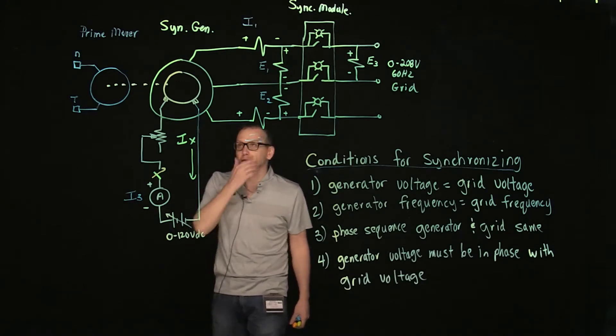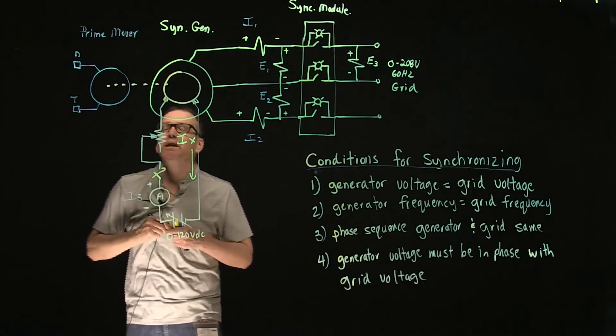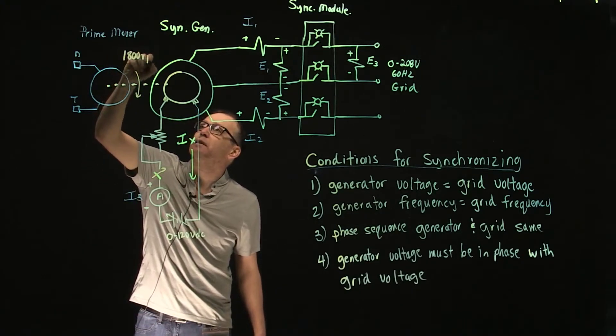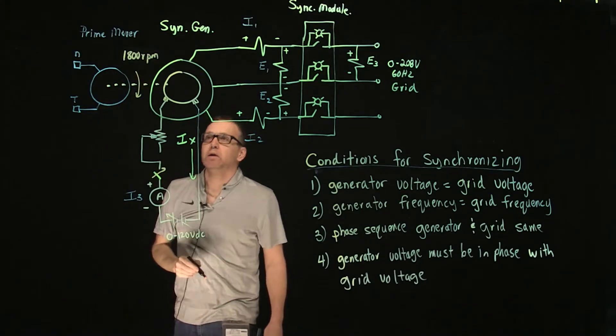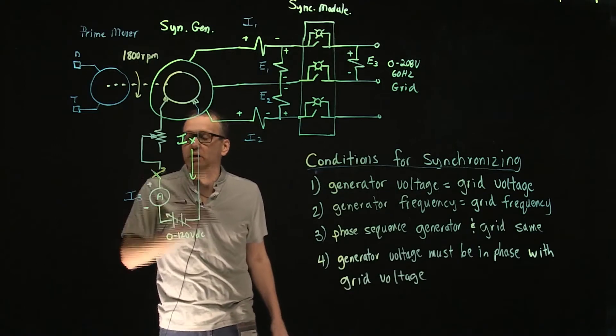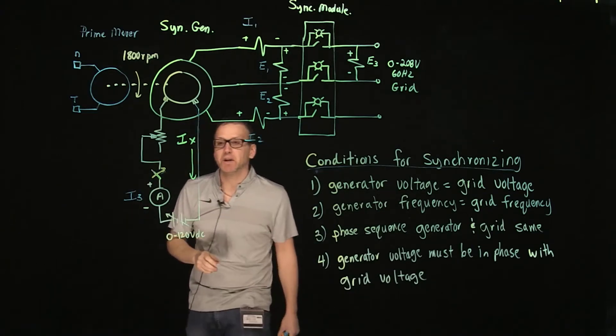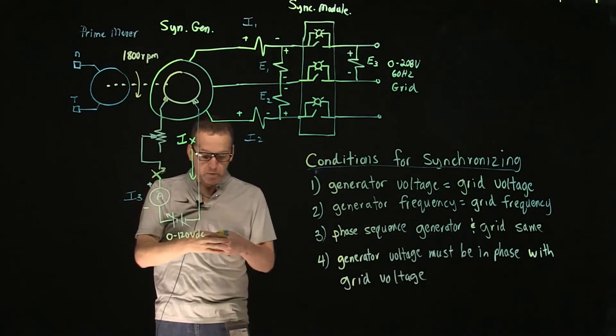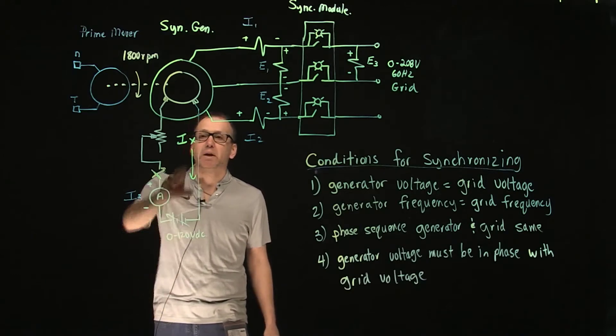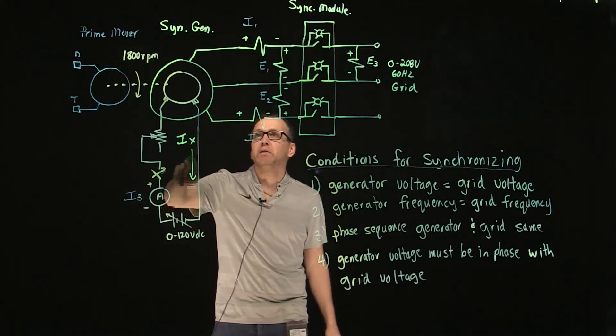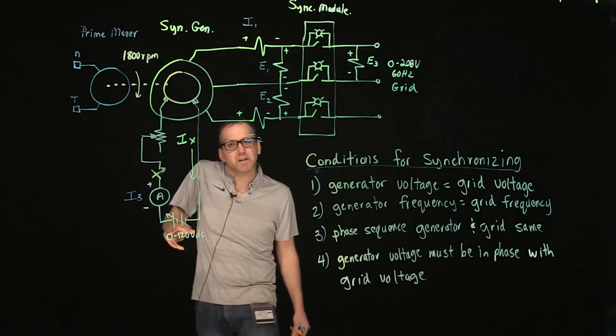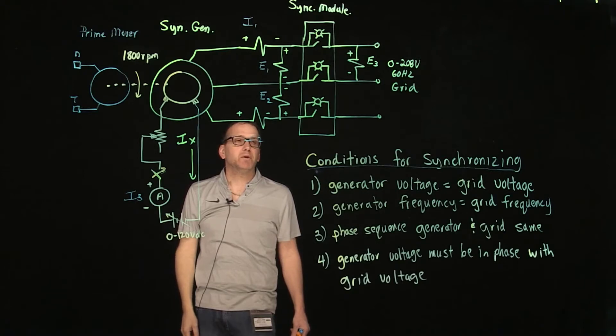The first thing we want to do is bring our prime mover up to rated speed, which in our case is 1800 RPM. Once the generator is running at rated speed, we can close the excitation switch. We can then adjust the output voltage by controlling the rheostat or the variable DC voltage to control the excitation current, which will change the output voltage.